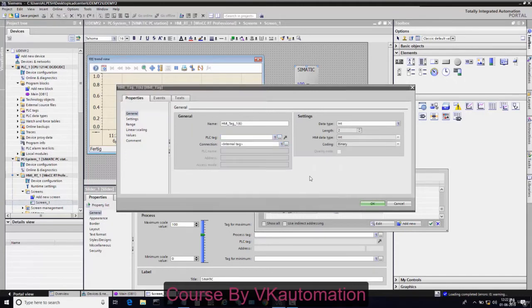Here I will pick one slider and connect one tag from PLC to this slider. We have generated MD20, so I will pick MD20 and connect data type real. Whatever value I change from the slider will send to PLC through this tag.